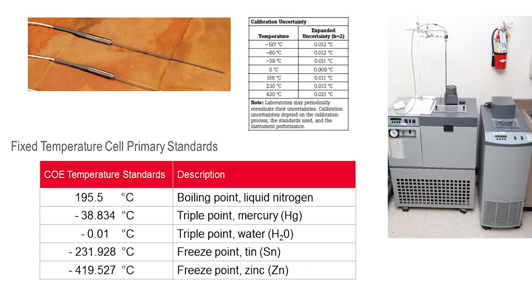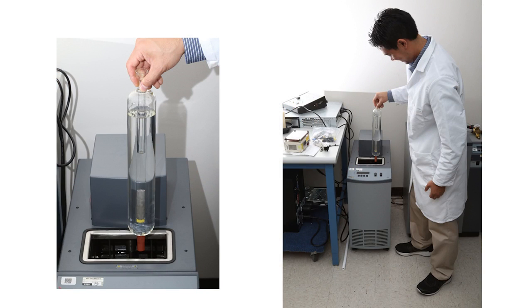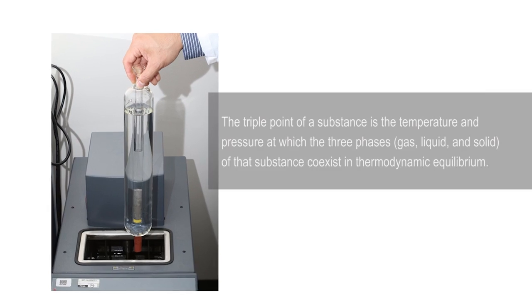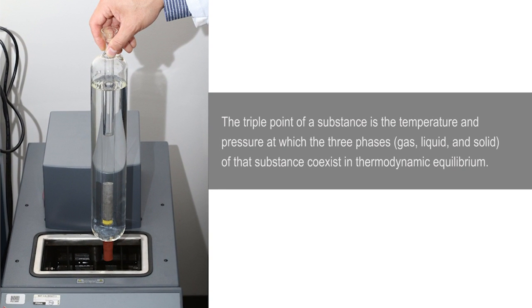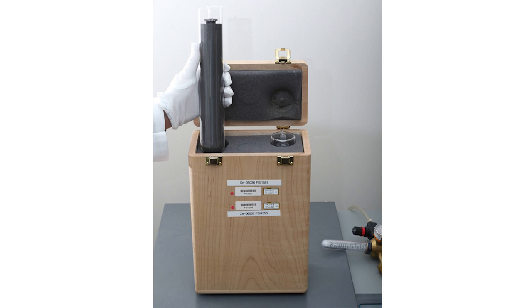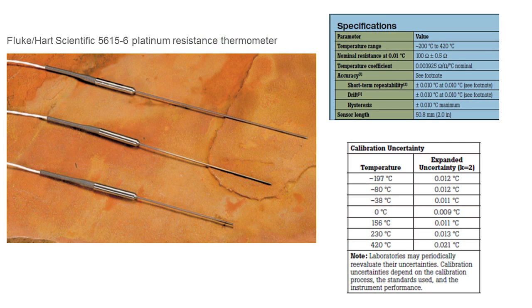This is the temperatures of several fixed point cells. These are actually primary standards. And this is one of our technicians putting in the triple point cell for water into the temperature bath. When you have the triple point, you have physical properties and you have an extremely accurate implementation of temperature. These are the cells which go into the temperature baths for tin and zinc. The very most accurate thermometers are platinum resistance thermometers, where you measure the resistance and then using the international ITS-90 tables, you're able to convert that to temperature.